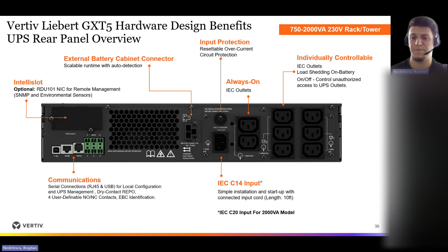And as I said before, an important capability of these Edge UPSs and also the GXT5 is that you can extend the standard runtime of the UPS by connecting such external battery cabinets to this unit. So if we take a look at this table, we can see exactly how dramatically the operation time of the UPS increases by connecting an EBC, or external battery cabinet.